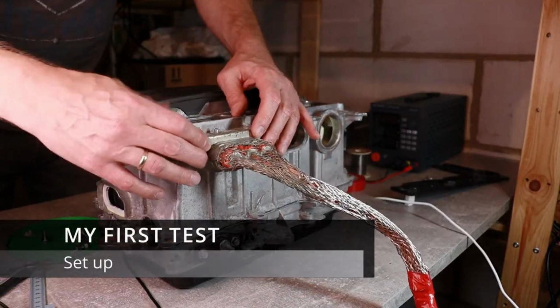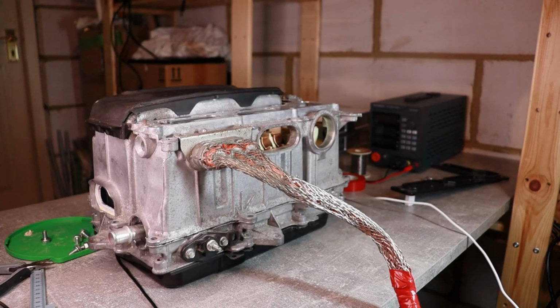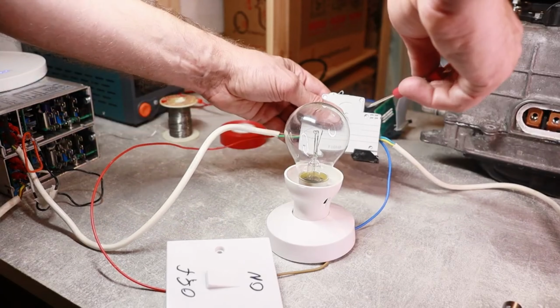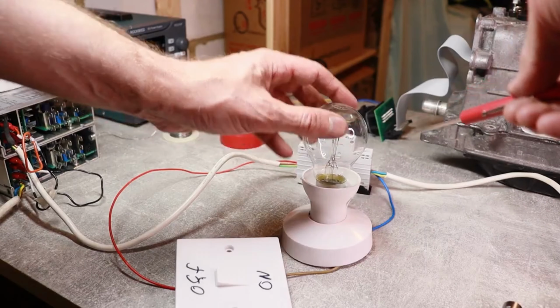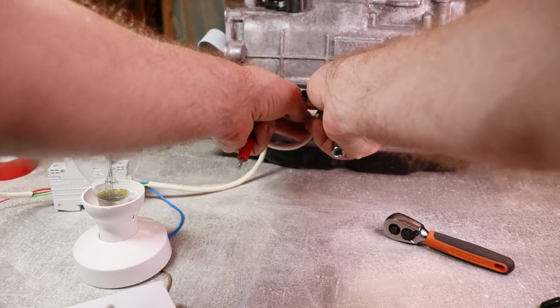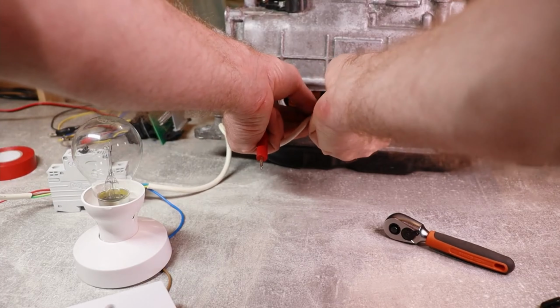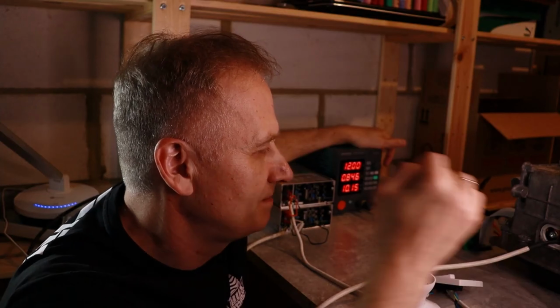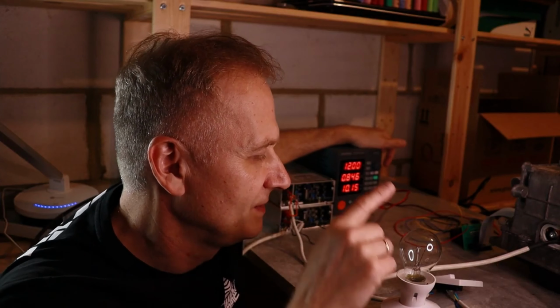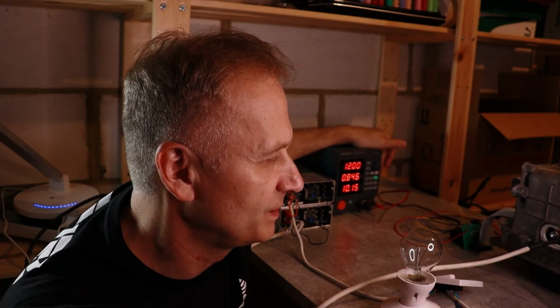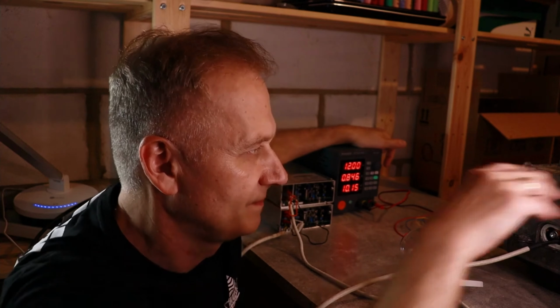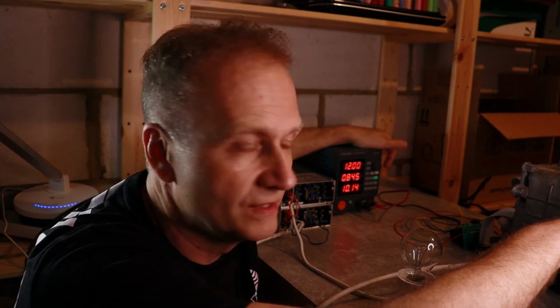Once the cable is there, we can actually start the test. At first, I've just connected the bulb as my pre-charge resistor, I've had a fuse and a switch. The switch will allow me to go from pre-charge mode to normal operation mode. Once I turn the supply on, the bulb should light up, and the current should be passing through the bulb, supplying the high voltage to the inverter.